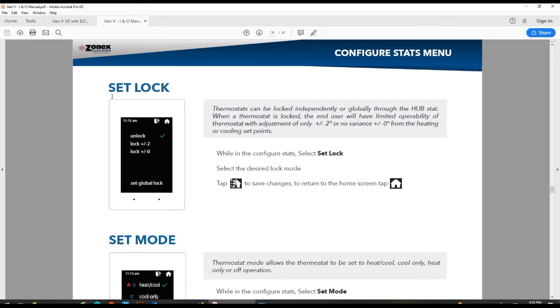Alright, if you choose or would like to lock out thermostats, you can lock them out individually and or globally. We offer 2 lock options. One is plus or minus 2 degrees from set point, or you can do what we call the no variance lock, or plus or minus 0 degrees. And this will completely lock out the thermostat and not allow them to change the temperature at all.